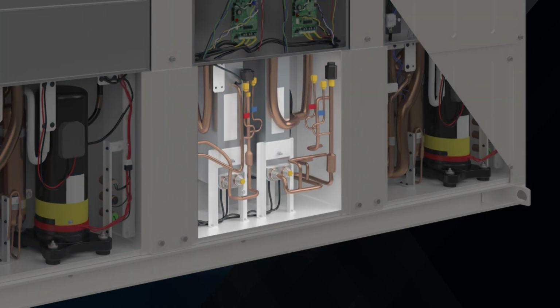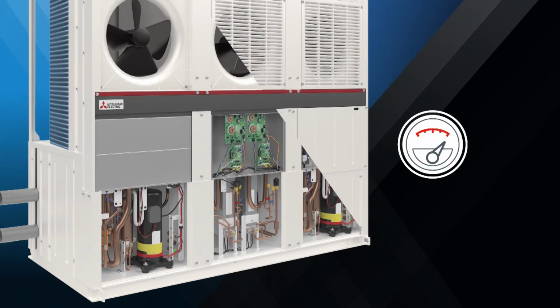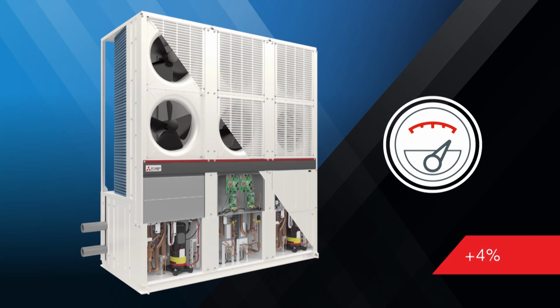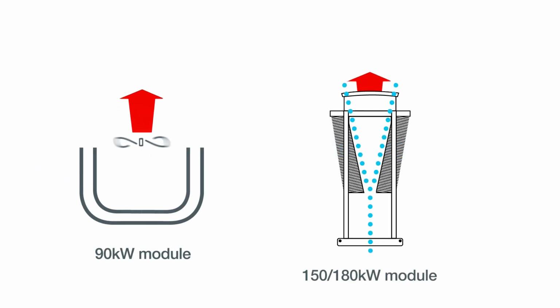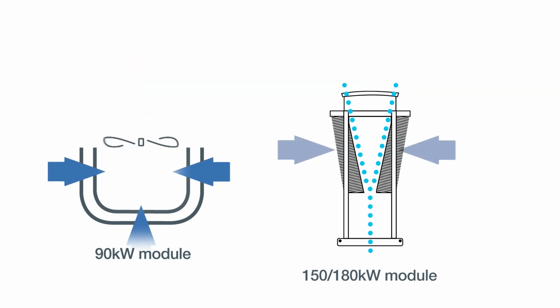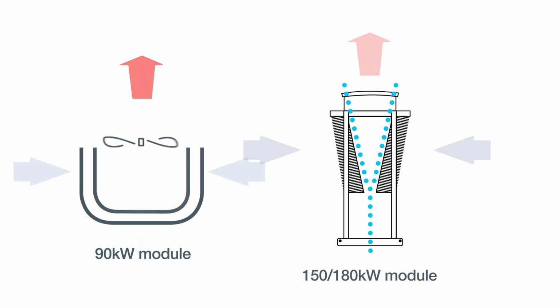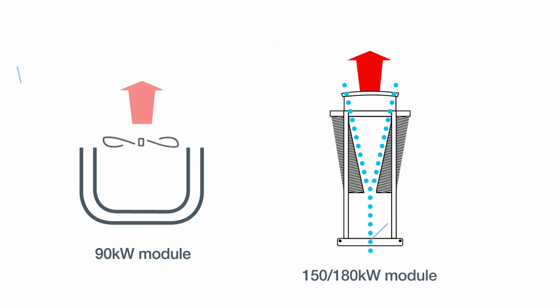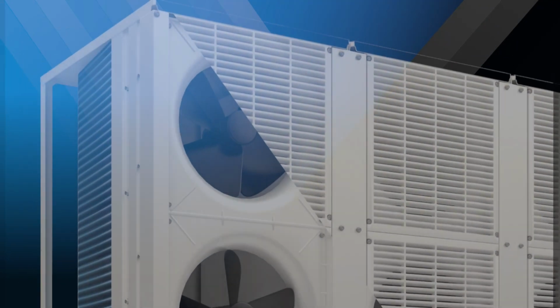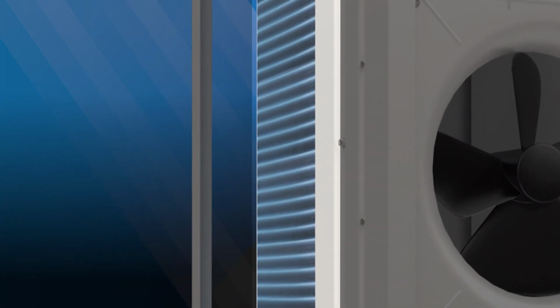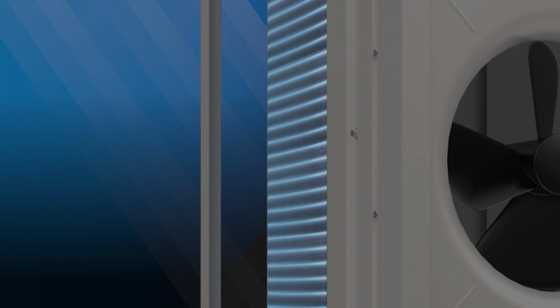Each compressor serves separate plate heat exchangers, and by modulating the evaporating temperature individually, overall system efficiency can increase by an additional 4% compared to single evaporating refrigeration cycles. The E-Series U and V-shaped heat exchangers also provide a greater surface area and a more effective intake airflow, adding to the efficiency of each system whilst keeping the units narrower than conventional chillers. Blue fin anti-corrosion coating on the heat exchanger is also provided as standard.